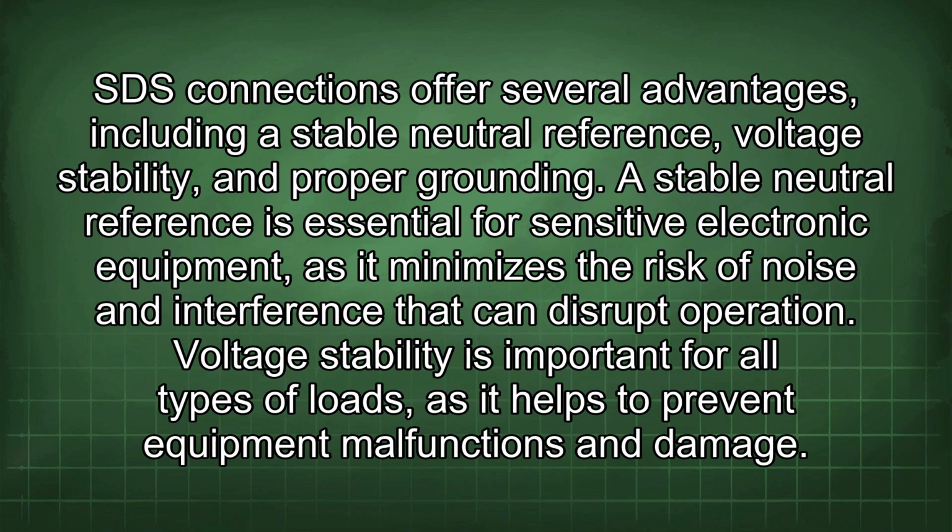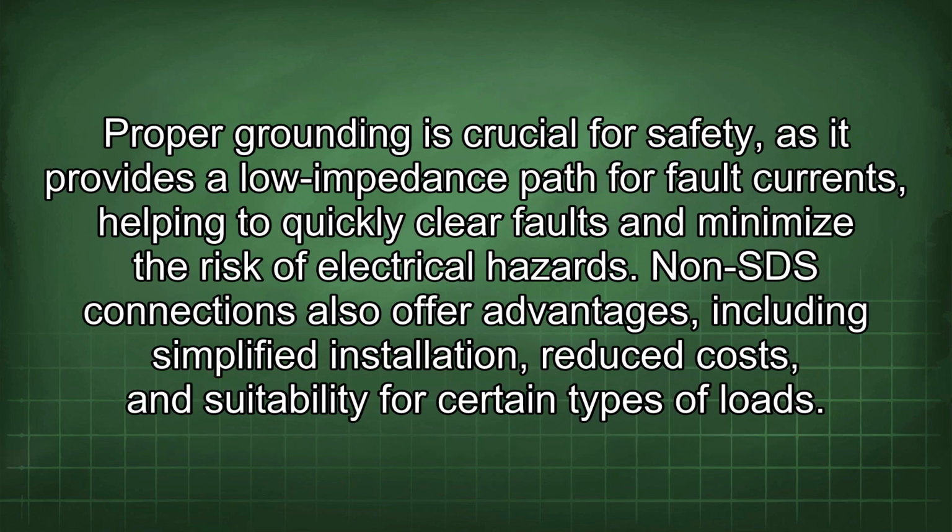SDS connections offer several advantages, including a stable neutral reference, voltage stability, and proper grounding. A stable neutral reference is essential for sensitive electronic equipment, as it minimizes the risk of noise and interference that can disrupt operation. Voltage stability is important for all types of loads, as it helps to prevent equipment malfunctions and damage. Proper grounding is crucial for safety, as it provides a low impedance path for fault currents, helping to quickly clear faults and minimize the risk of electrical hazards.